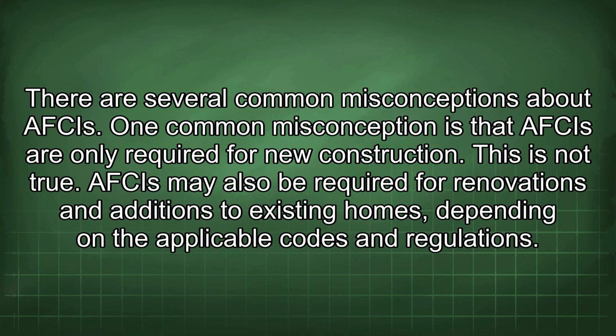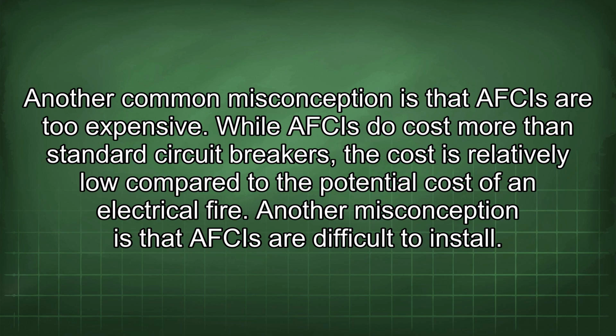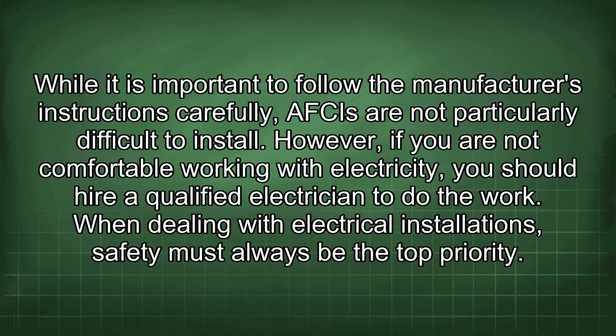There are several common misconceptions about AFCIs. One common misconception is that AFCIs are only required for new construction. This is not true. AFCIs may also be required for renovations and additions to existing homes, depending on the applicable codes and regulations. Another common misconception is that AFCIs are too expensive. While AFCIs do cost more than standard circuit breakers, the cost is relatively low compared to the potential cost of an electrical fire. Another misconception is that AFCIs are difficult to install. While it is important to follow the manufacturer's instructions carefully, AFCIs are not particularly difficult to install. However, if you are not comfortable working with electricity, you should hire a qualified electrician to do the work.